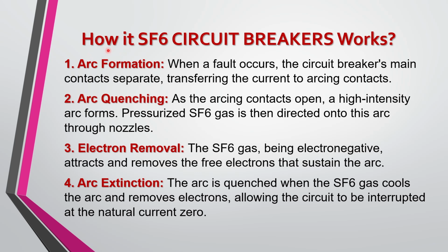Let's explore how SF6 circuit breakers work. So, in the situation when the fault occurs, arc formation takes place. So when a fault occurs, the circuit breaker's main contact separates, transferring the current to arcing contacts. Arc quenching. As the arcing contacts open, a high intensity arc forms, and pressurized SF6 gas is then directed onto the arc through the nozzles.